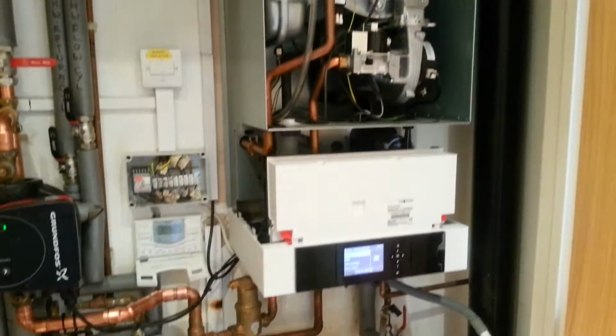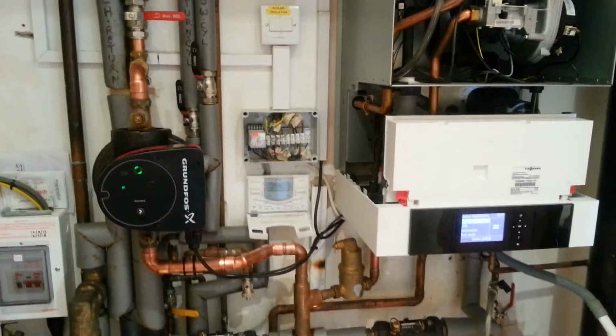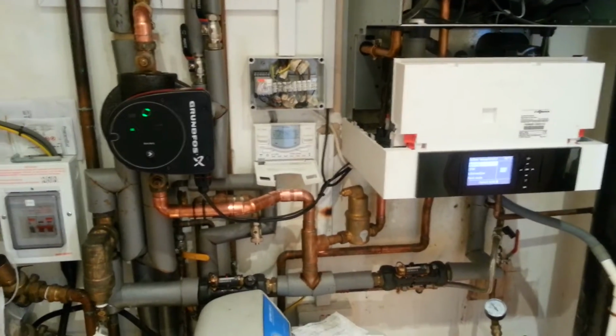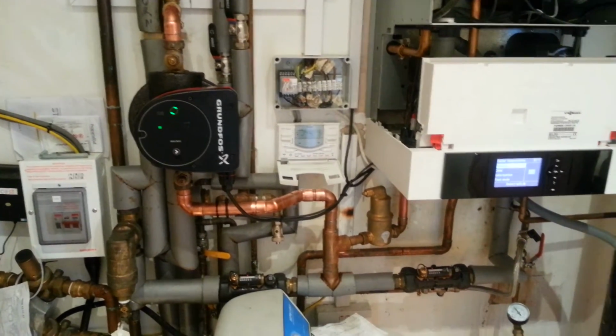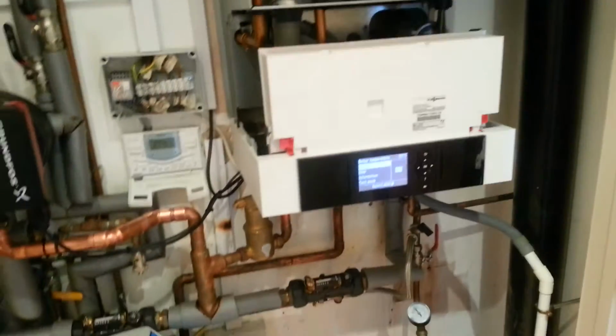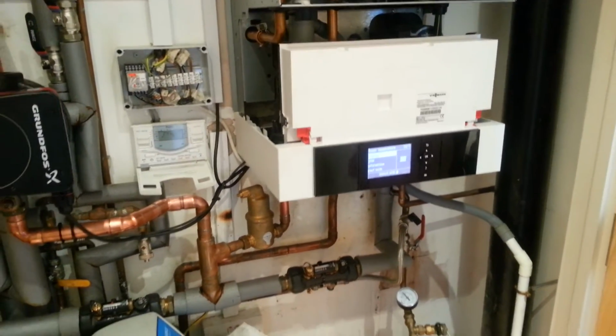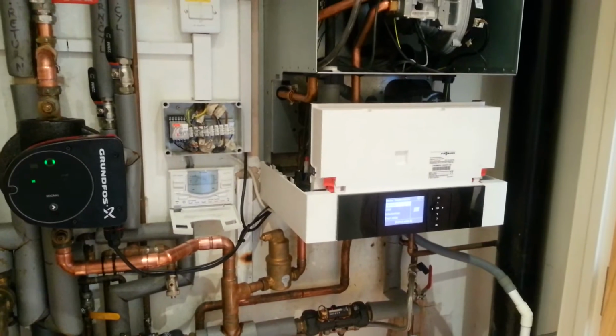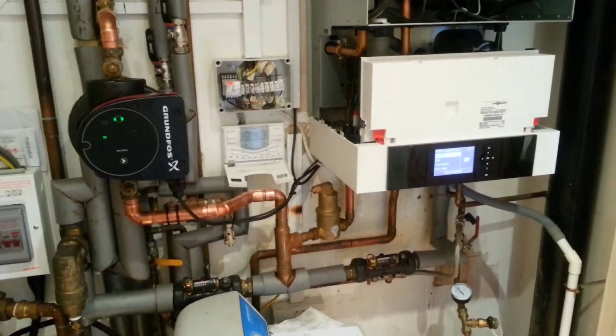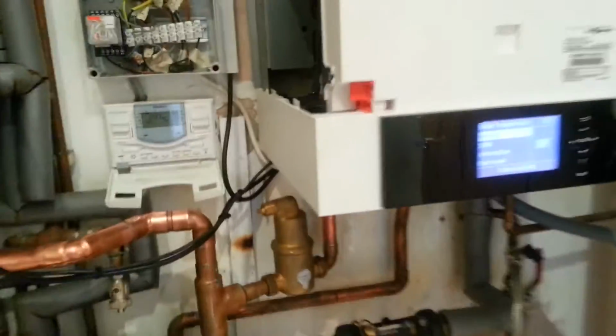Today's job is to find out why we're getting slow heat up of hot water. I've already fixed the problem and found the cure. Viessmann 200. It's in a large house, 35 kilowatt boiler. It's about 20 kilowatts approximately for the heat load of the house. I've used close coupled T's for hydraulic separation.